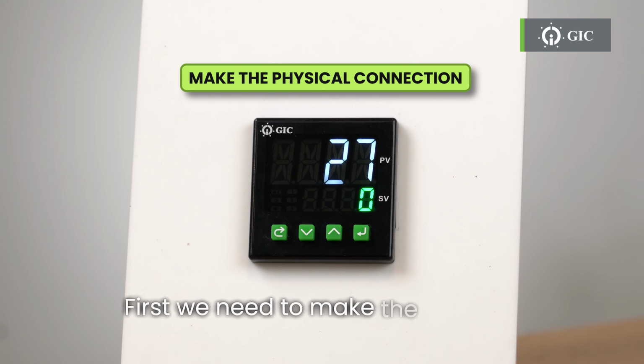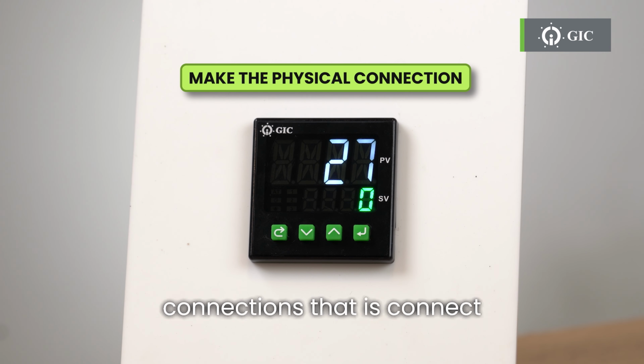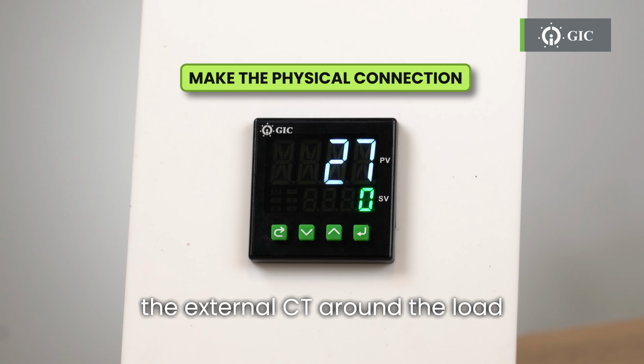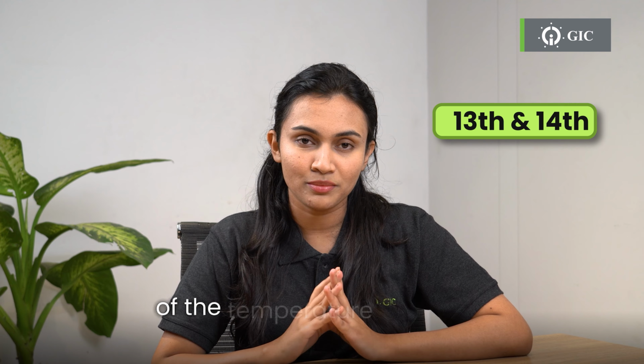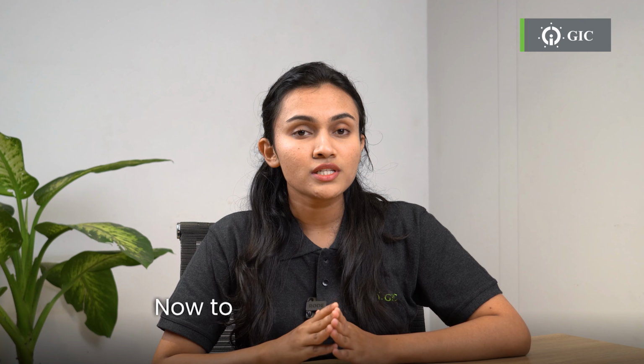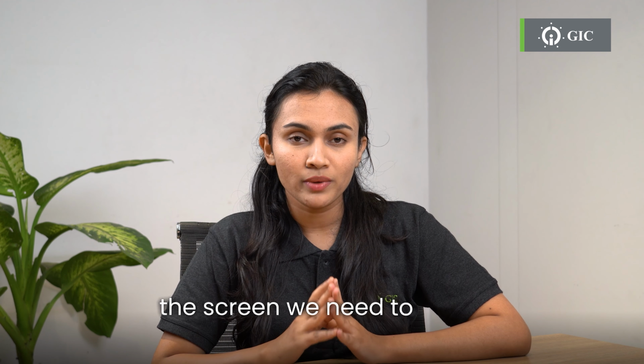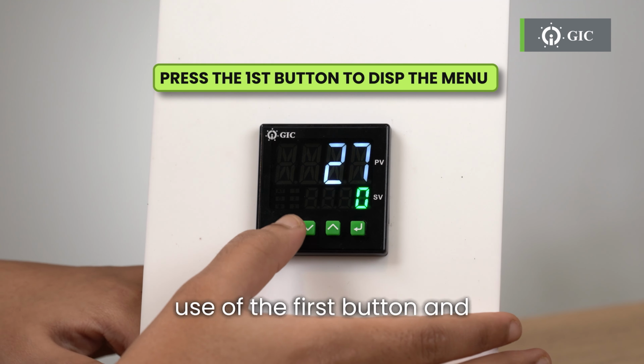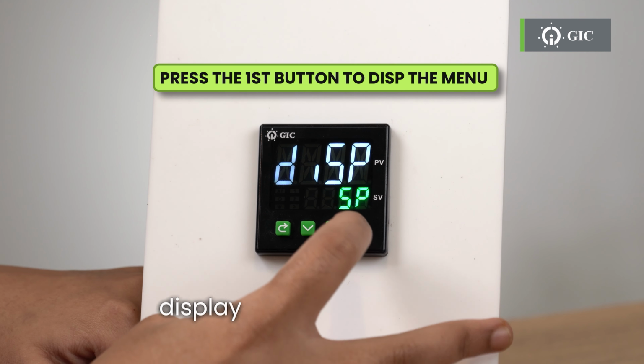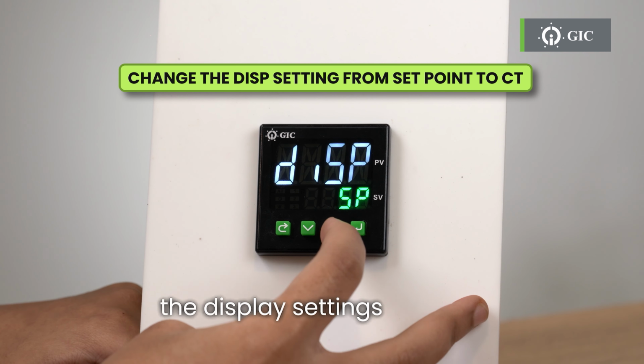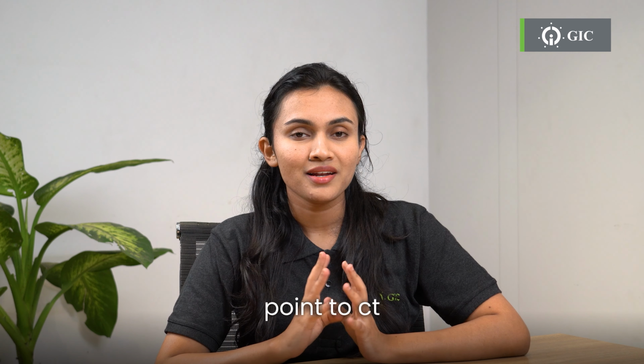First, we need to make the physical connections, that is, connect the external CT around the load to the 13th and 14th pin of the temperature controller. Now, to display the current on the screen, we need to make use of the first button and press it once to see the display settings and change the display settings from set point to CT. Now we can see that the CT is being shown on the display.